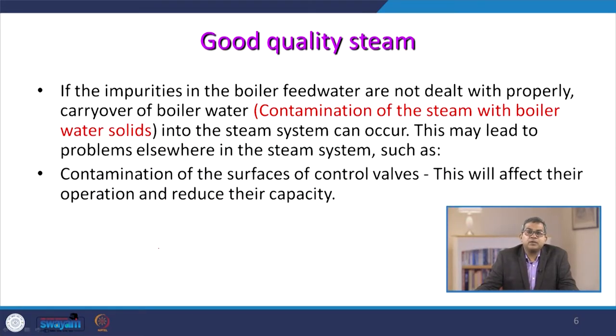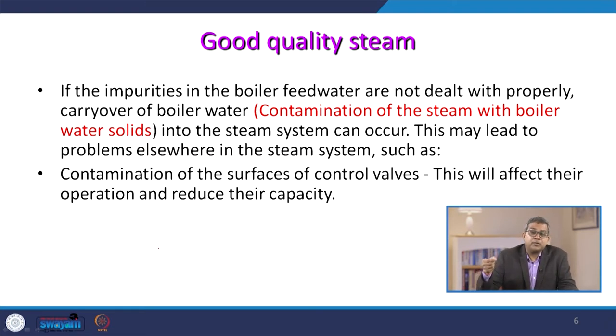For good quality of steam, if impurities in the boiler feed water are not dealt with properly, then carryover of a boiler — meaning contamination of steam with boiler water solids into the steam system — can occur. This may lead to problems elsewhere in the steam system. Even small metal particles may participate in chemical reactions. These contaminants may affect control valves by deposition, corrosion, or erosion, and will affect their operation and reduce their capacity.